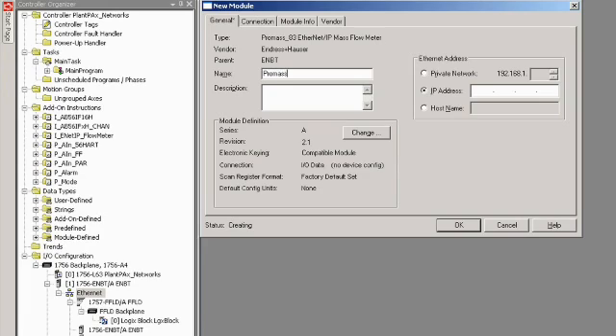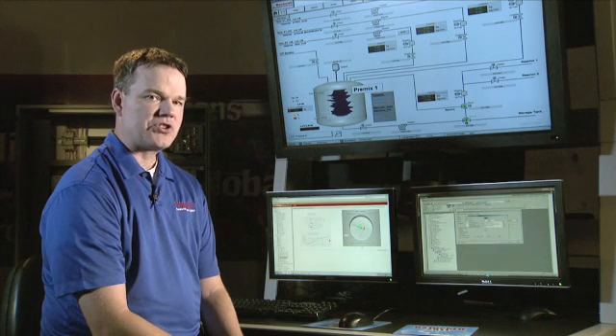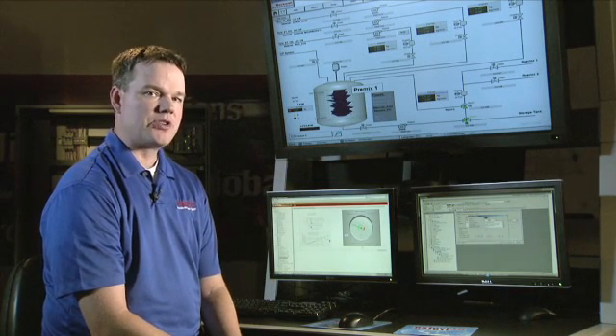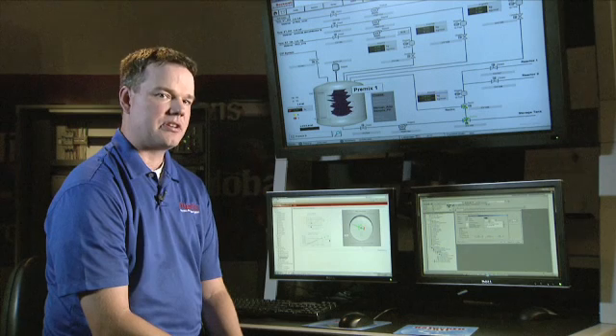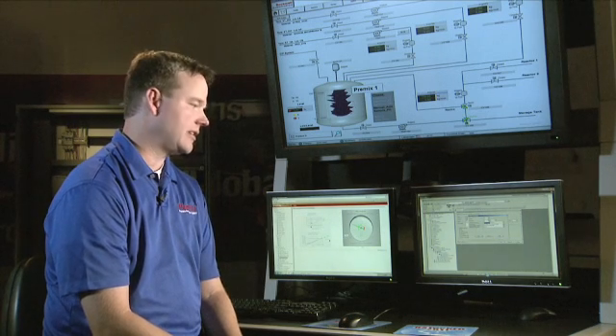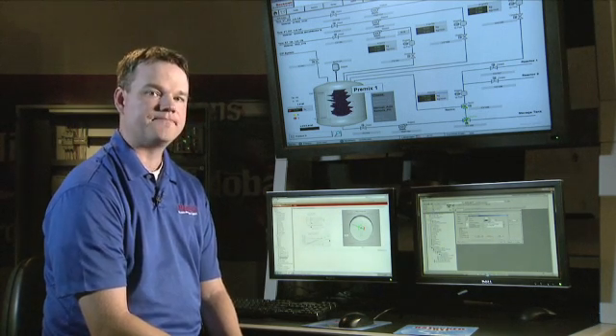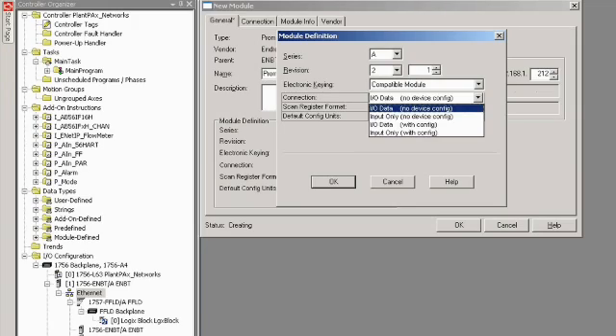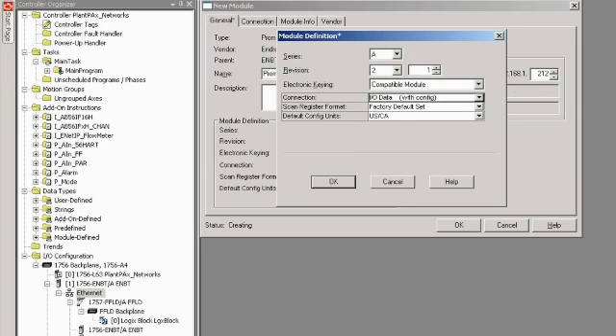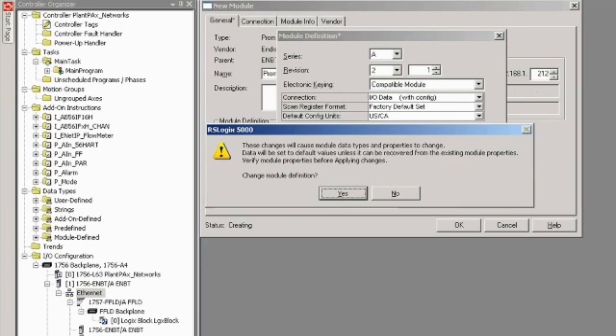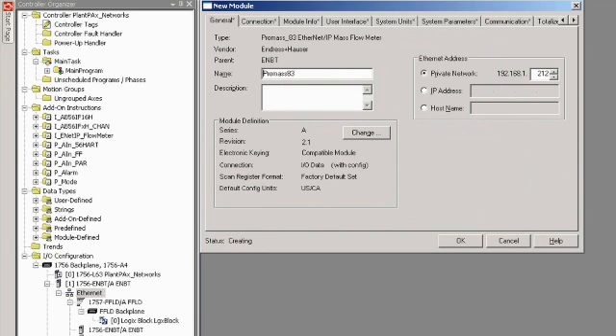Next, give the device a name and an IP address. You can get this IP address from the device itself. Make sure that the module definition is set to the latest revision, and change the Connection Radio button to IOData with Config. After you accept those changes, additional tabs will pop up, which will allow us to completely configure the device.